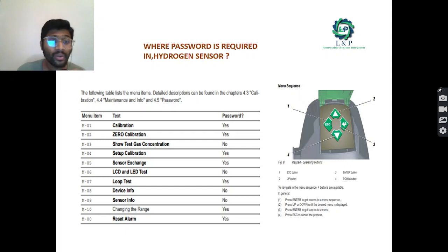We should know where the password settings are. We have an option inside it. If you want to do the calibration, you need to put in the password. If you want to do sensor exchanges while it is alive, you need the password settings. If you want to do the loop test, you need to put in the password. And if you want to change the ranges or reset the alarms, you need the password. So to access all these points inside the sensor, you need the password.